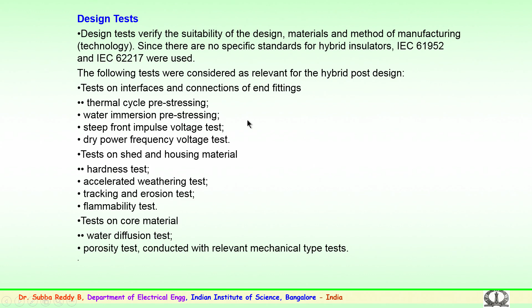Here again, similar to the standards prescribed, the thermal cycle pre-stressing tests, water immersion pre-stressing. Steep fronted impulse voltage test is an electrical test. Dry power frequency voltage test, again a withstand test at 50 or 60 hertz. Tests on shed and housing materials: here again, being a polymer material, it has to be tested for hardness. Accelerated weathering tests, tracking and erosion of the silicone rubber material, flammability test, and for the core, tests on the core include water diffusion test and porosity, conducted along with relevant mechanical type tests. So, these are some of the design tests which, with reference to IEC 61952 and 62217, are generally followed for the hybrid type of insulators.